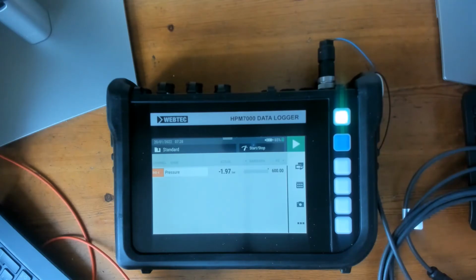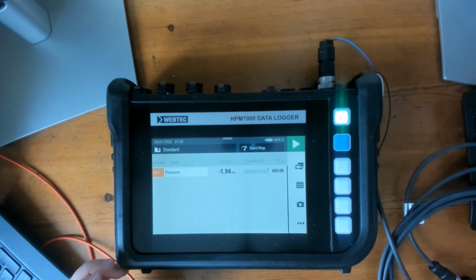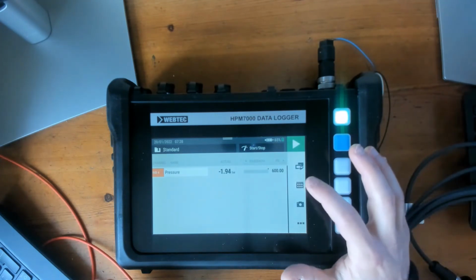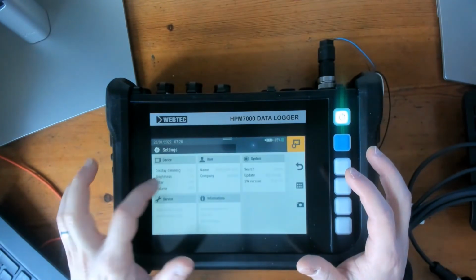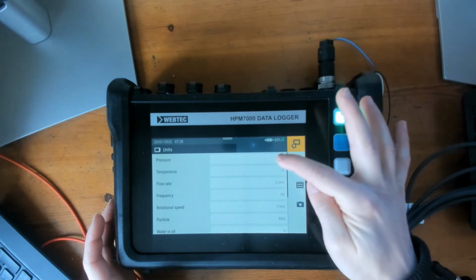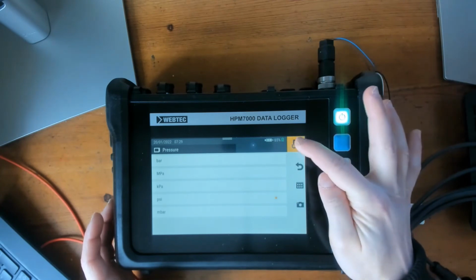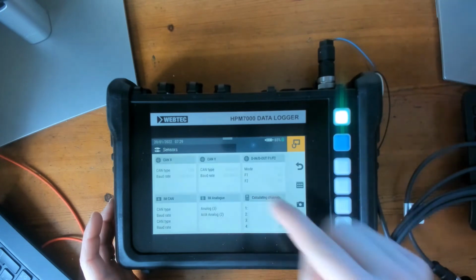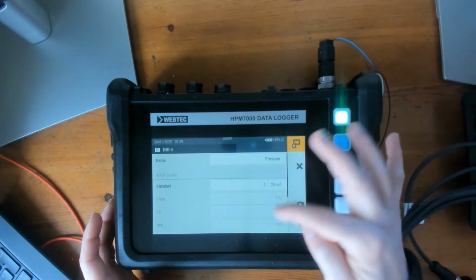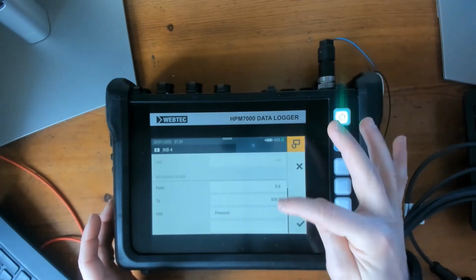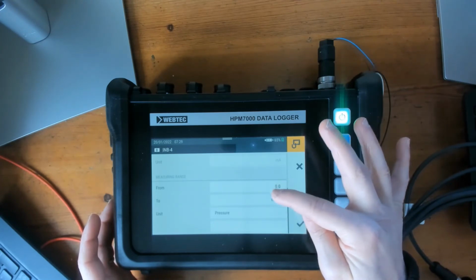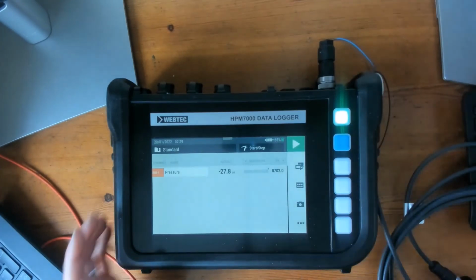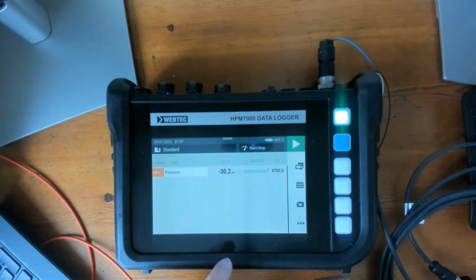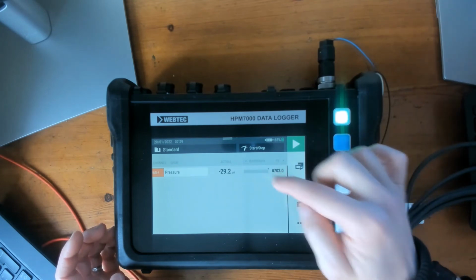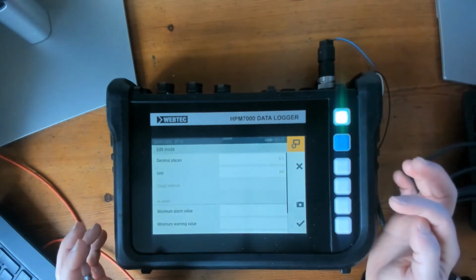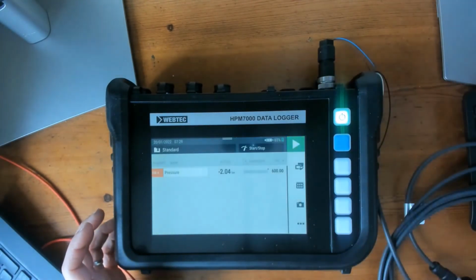So another way to scale a PSI 4 to 20 milliamp pressure sensor is to change the units of the device to PSI. From settings, device, units, pressure, PSI. And then go to the sensor, the analog input, and select the pressure units and scale it on the PSI values. However, that will mean that all the pressure channels will be shown as PSI, but then you can change the units for individual channels from the edit channel menu if you want to do that. There you go.